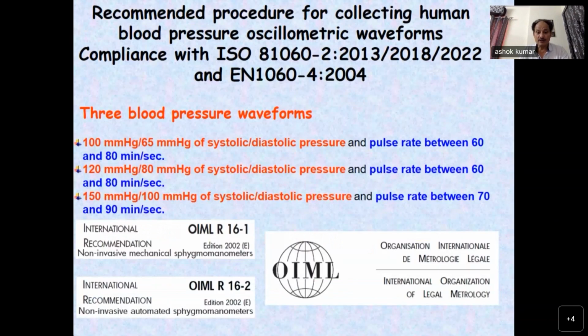81060. The second part, which Ashutosh ji knows well, is that we are now following the OIML guidelines, International Organization of Legal Metrology, R16.1 and R16.2, and these are still not clear about the dynamic calibration of blood pressure devices, because most of the procedure required for type approval is based on the static mode of calibration of the pressure sensor. But since it is based on an algorithm, it requires dynamic mode of calibration. But with ISO 81060, which we have now, I believe we can do that part.